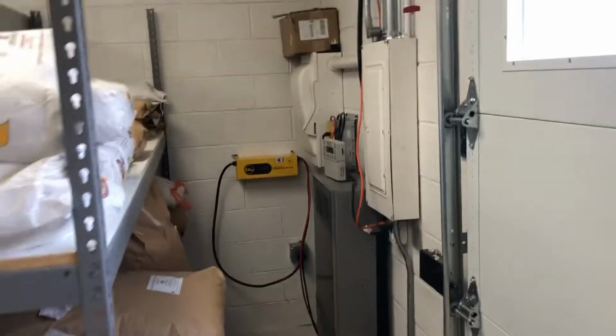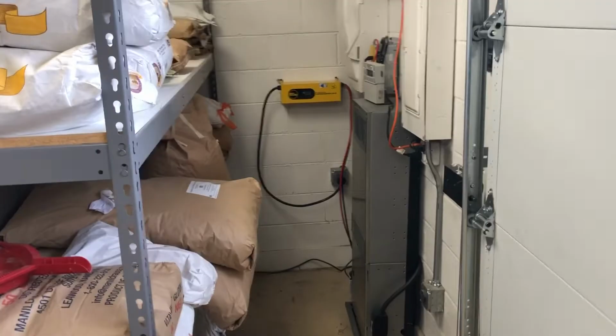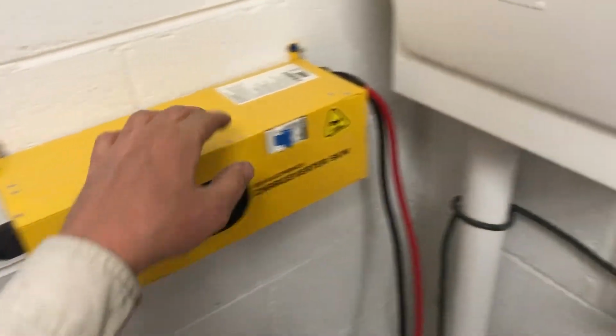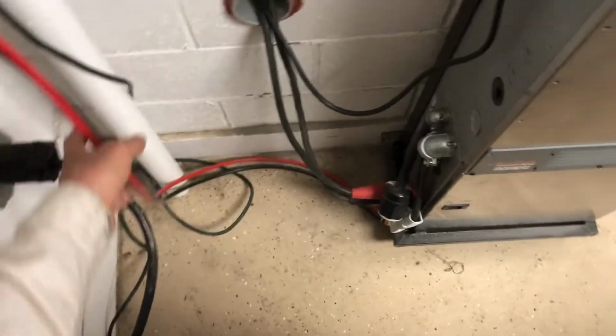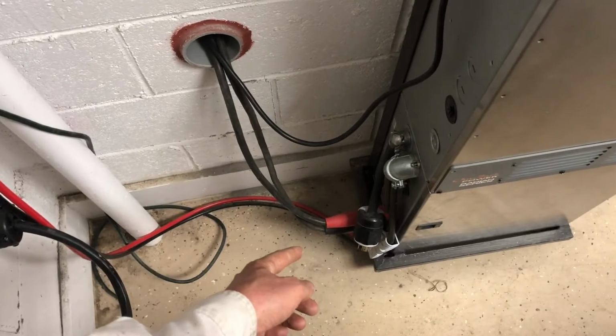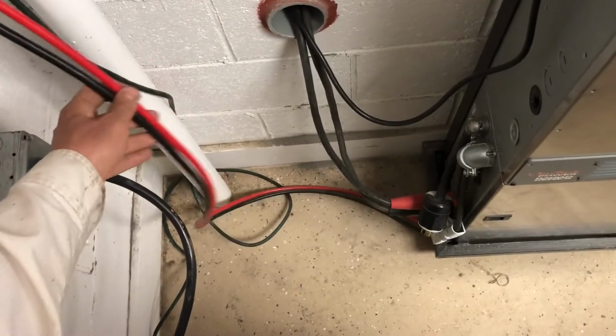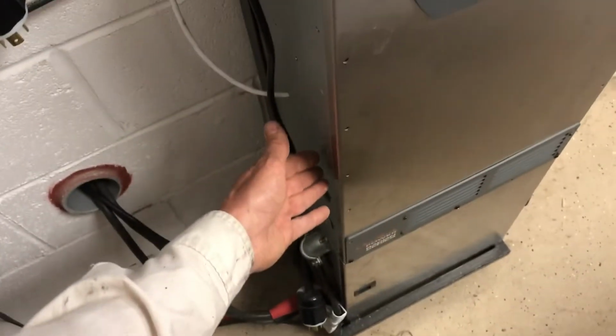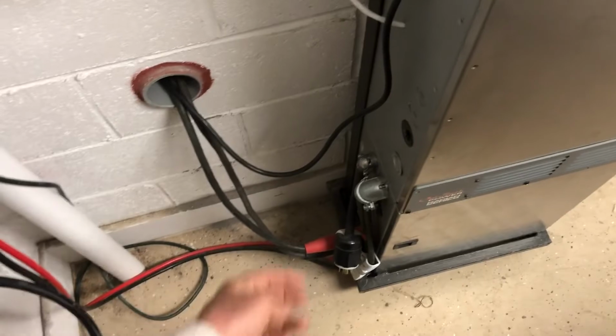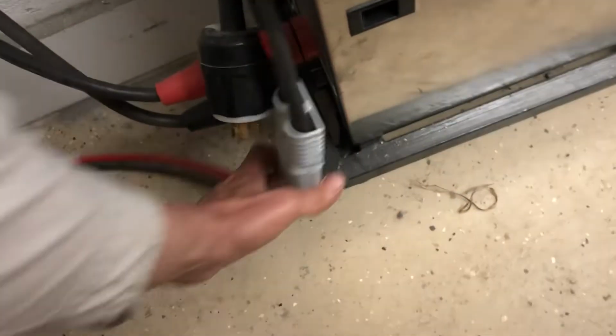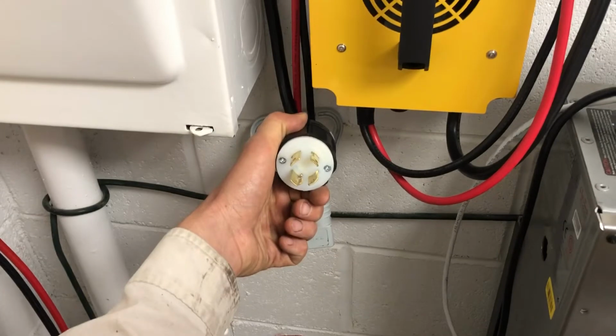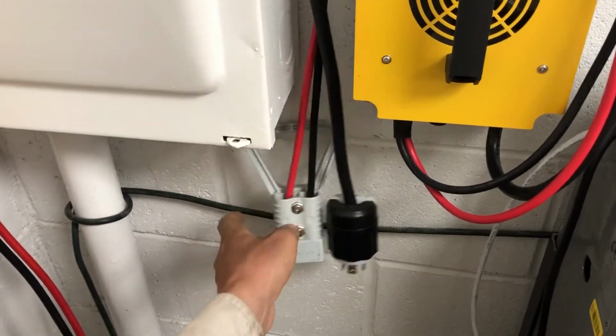Okay, so here's the mechanical area, if you will. It's a little kind of warehousey in this garage, pretty nice and organized. And so that 10 gauge cable is running this charger, which is directly connected to basically the bus inside the Outback here. And so there's a common connection between this inverter input, the battery, and the line side of the DC for the inverter inside there. And I have a 175 amp Anderson on here. And I also have a backup charger here with the same plug arrangement. So it's a 30 amp twist lock and 175 amp Anderson connector.